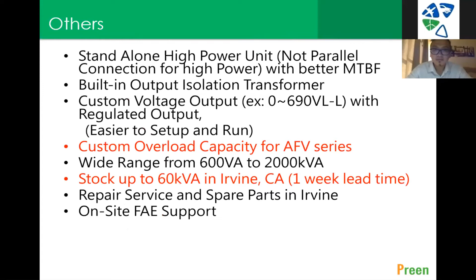So let's see here. If you are using some other brand of supplier for like 60 kVA, you may have to parallel 3 units with a master-slave structure. But with Preen, because we design with a single unit machine, we have better experience in large kVA. So we design the 60 kVA as one single machine. The advantage is that if you design one single machine of 60 kVA, the mean time between failure, MTBF, will be better, which means the reliability will be better as well.